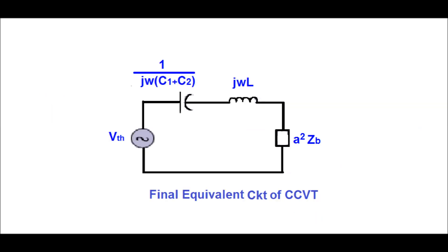The final equivalent circuit of CCVT referred to the primary side has been shown in this figure. Here ωL = 1/(ω(C1+C2)). The voltage drop across C is neutralized, and the relay sees the actual voltage to be measured.